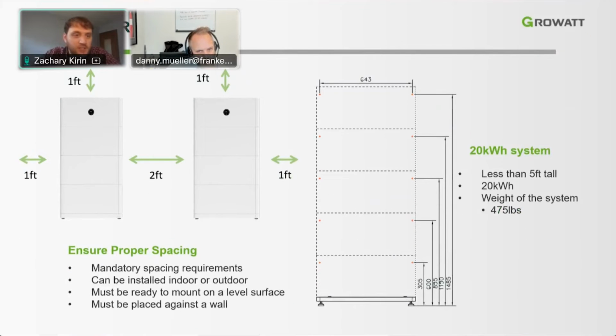The APX has some very similar requirements as far as spacing goes. Each of the battery pack spacings would be as follows. It needs 1 foot in each dimension, unless it's going between 2 APX batteries which are installed together. Then a 2-foot separation is the recommendation from our manual. So each of those battery packs can be installed within 2 feet of each other, or outside of 2 feet of each other, I should say. So there are the mandatory spacing requirements.